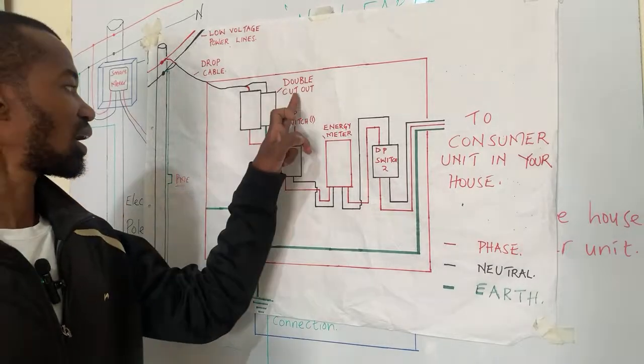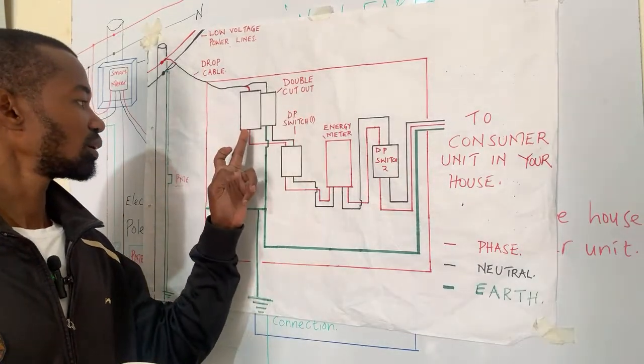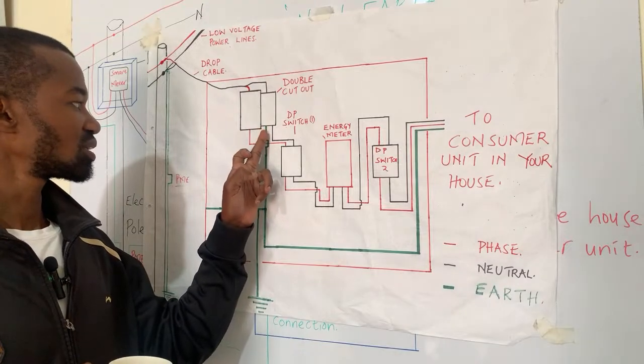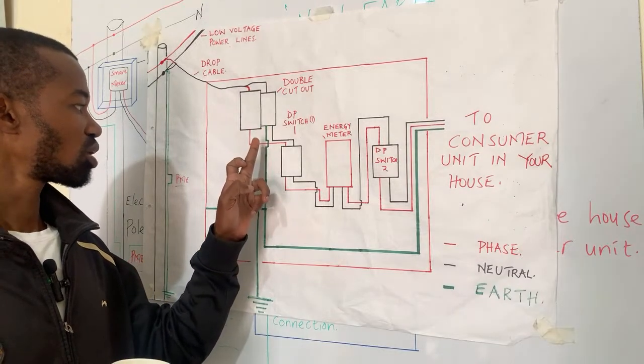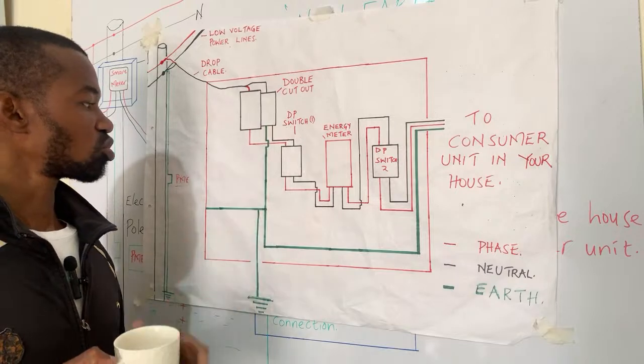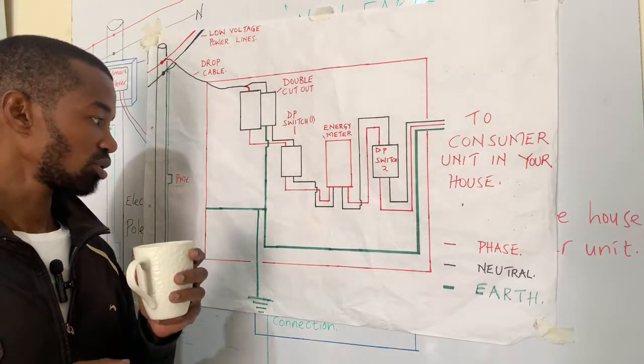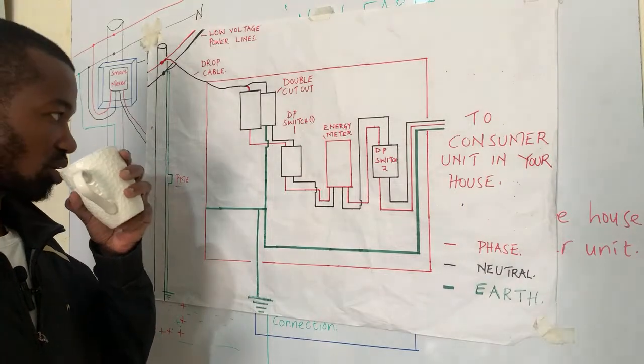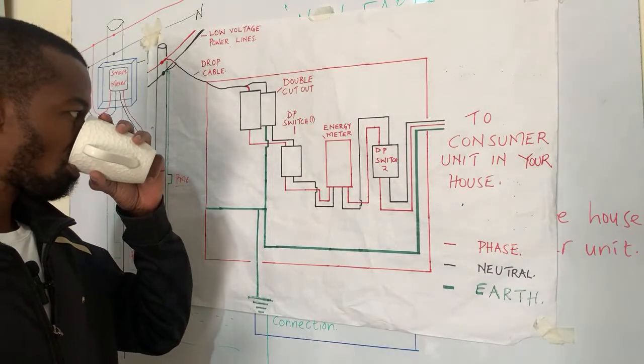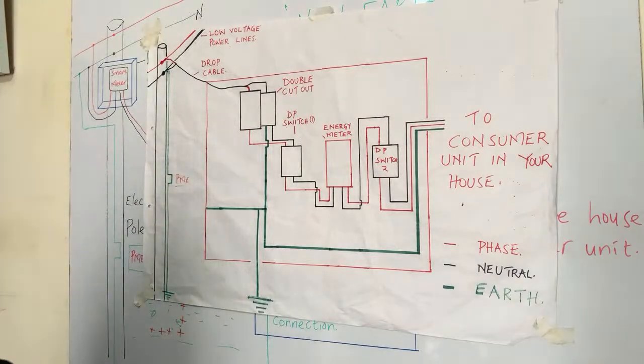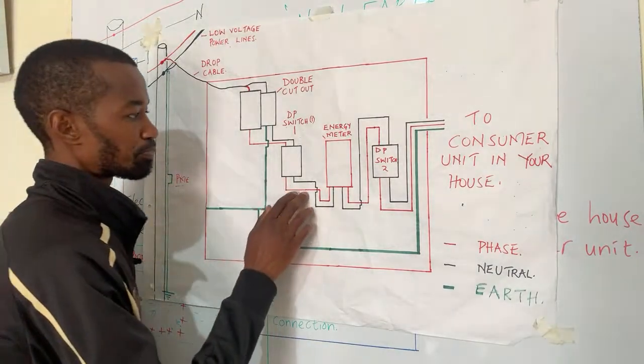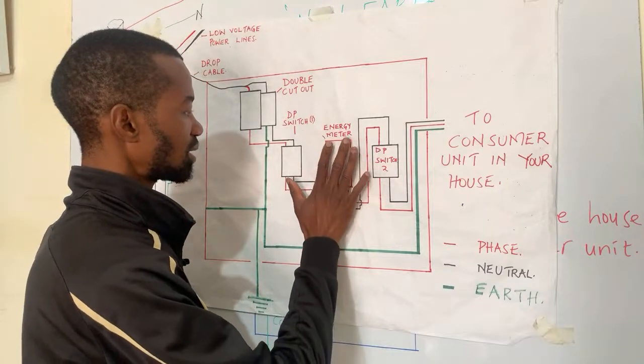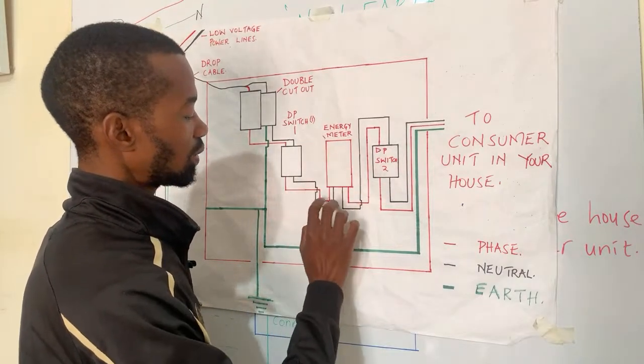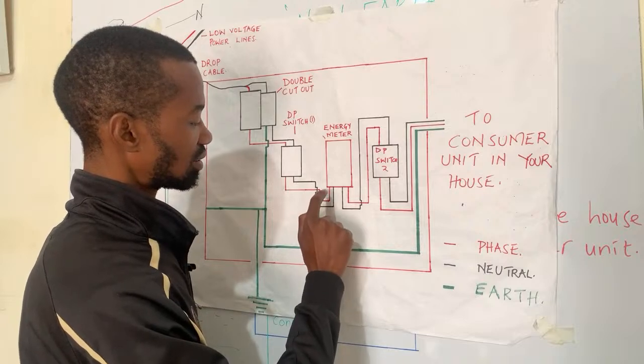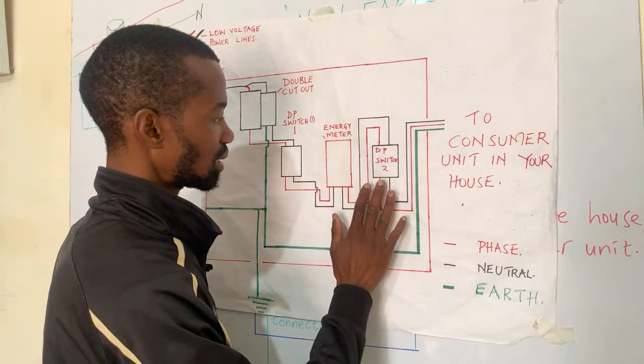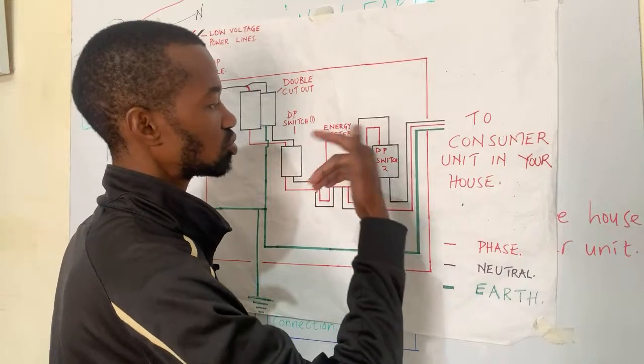So the connection here at the double cutout will be like so, or if it is a single cutout whereby you have the neutral, then the earth and the neutral will be looped there. This is before the meter box, I mean the energy meter. And then from there, from the energy meter, we will have the connection of the phase and the neutral all the way to the DP switch, and then from there to the consumer unit.